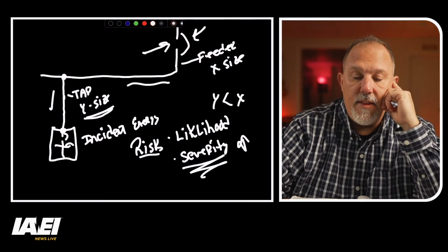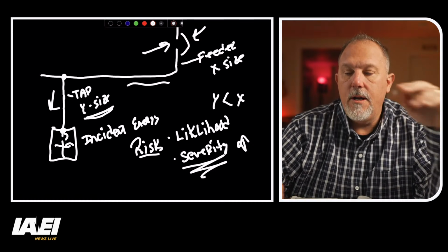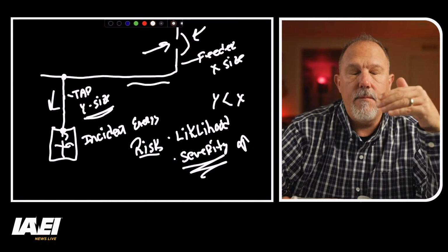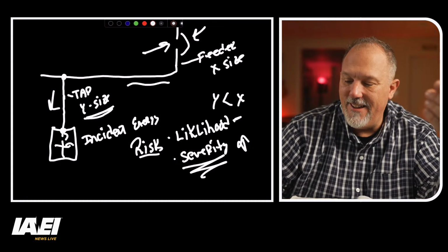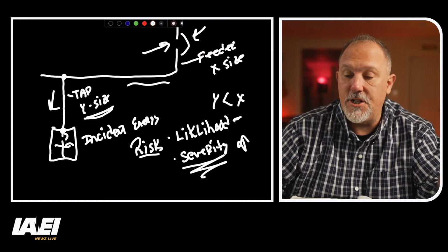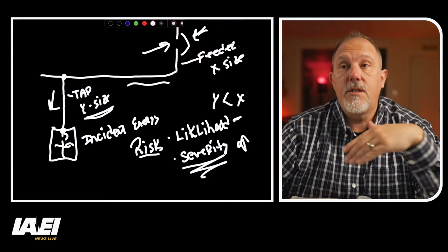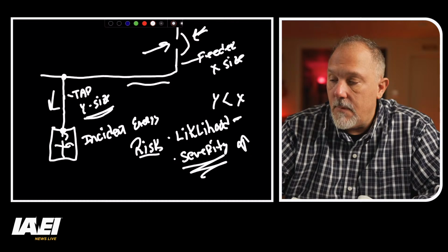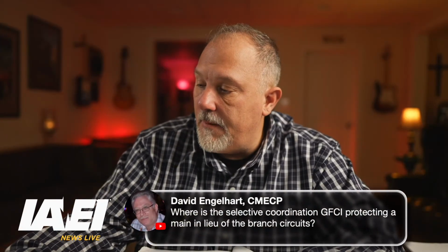You add this conductor length, that conductor length, my arcing currents are going to be lower. I have a high likelihood of not being in the instantaneous region of my protecting overcurrent device. So I have to think about the higher severity in those applications. Very similar to your service entrance conductors, which will have the utility transformer. You have unprotected conductors landing in a panel board, and we have barrier requirements there.